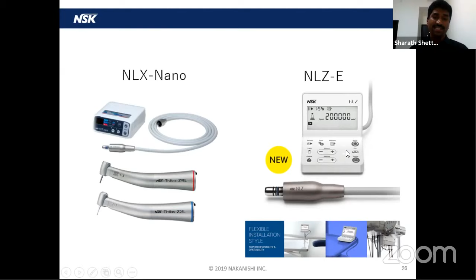It has a constant speed. Constant speed in the sense, generally when you use an aerator handpiece, when you press the burr on the patient's tooth, the speed reduces. Although it runs at 4 lakhs RPM, it will come down. But here in this handpiece, whatever load you give, the speed will remain constant because the power is generated by the electric supply, not by the compressor air. Reduced noise level. The noise level is comparatively very less as compared to your aerator handpiece.